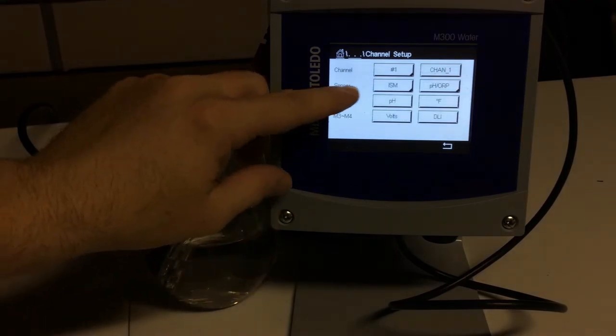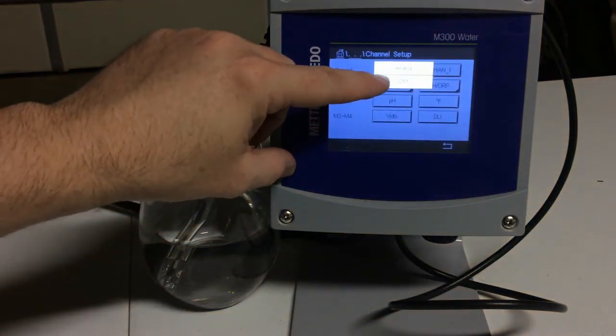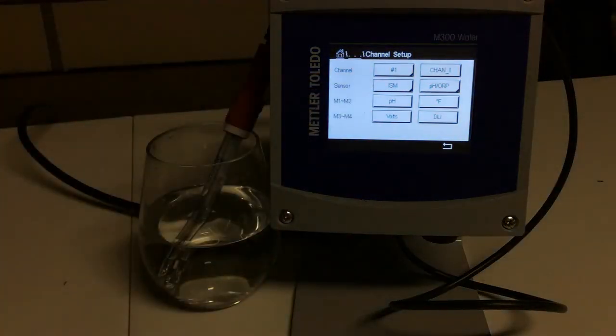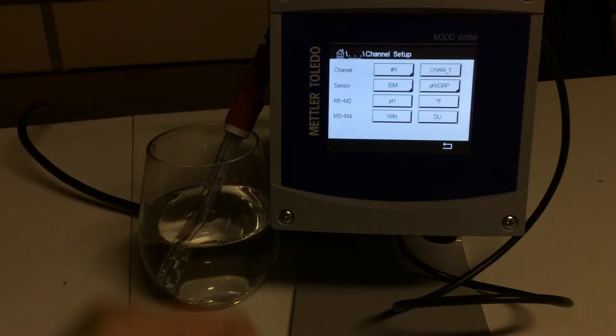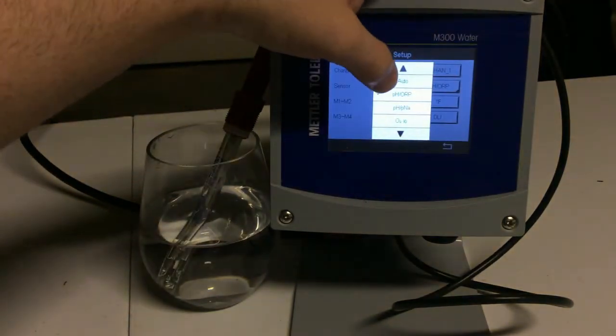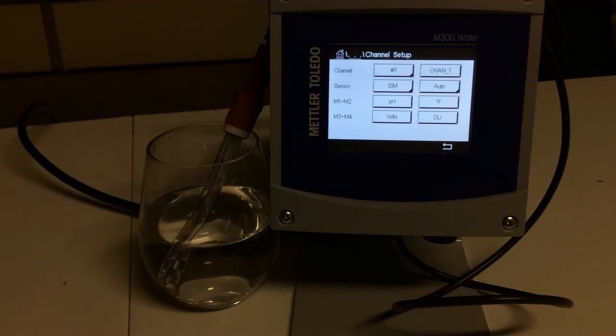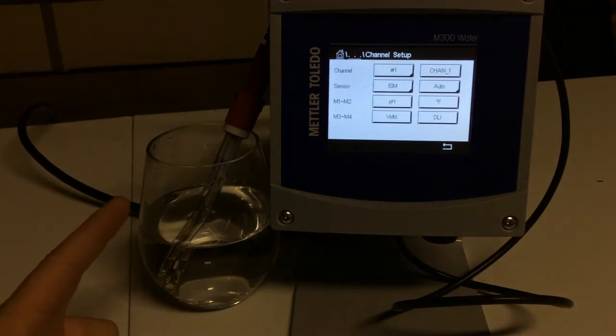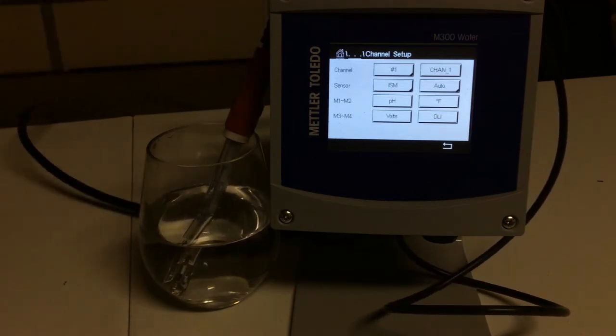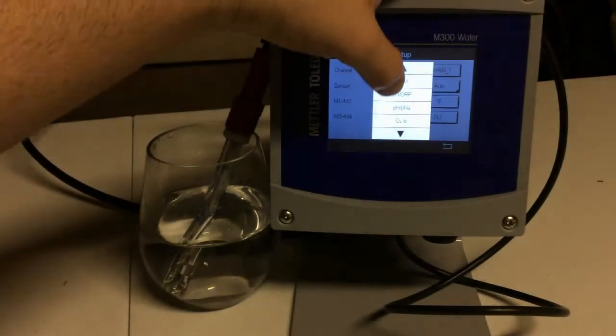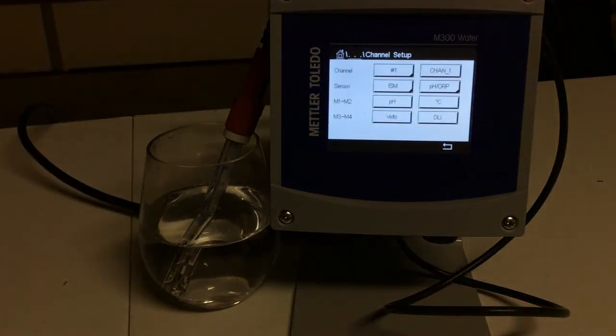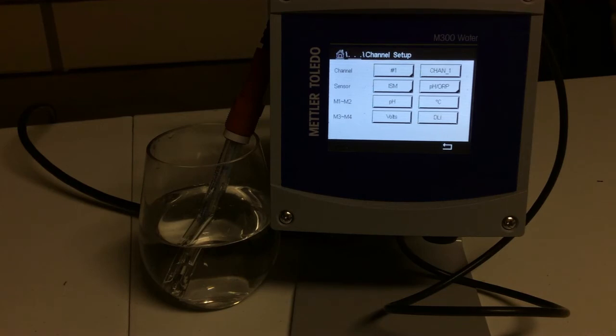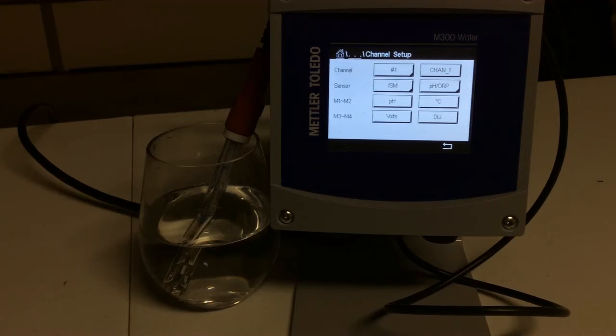The sensor, we have ISM. We can also do analog if it was analog, but we have ISM. And our measurement range over here is pH ORP. Now this is something that you can change. I can set it at auto, and when it's set at auto like that, no matter what sensor you would plug into it, as long as it has that same connection on the cable here, it's going to automatically read it and start measuring for you. So if you wanted it to only be for pH, we can set that pH ORP, and now if somebody were going to try to put in a conductivity or DO, it would give an error message, and it would not read. So it just helps people, especially if you have this two channel, we have one at pH, one at conductivity, it helps people from accidentally switching those channels.